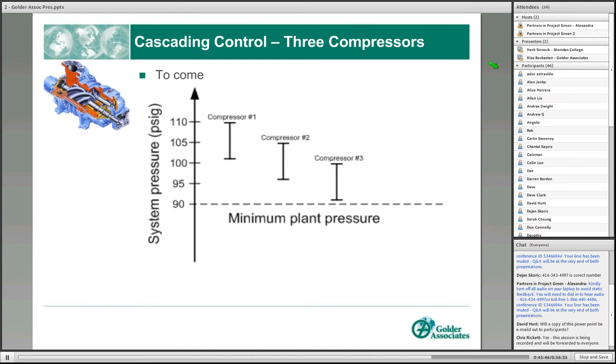So when the plant starts up, you would bring the compressors on, and once you're up to pressure and discharging into the plant, depending on the consumption levels of air, you would, in a cascading manner, run with 1 compressor, then kick in the second and the third. As compressors are controlled by their own discharge pressure in the cascading style, you end up with a large band of pressure variation in the plant depending on consumption. At very low loads, you might be operating on 1 compressor but generating about 110 psi. With a plant running full out, you might be dropping the pressure down to 90 psi. So you end up paying a lot of penalty with the pressure variation.